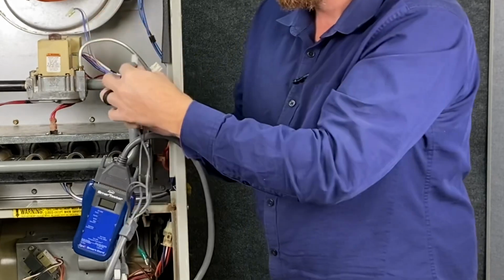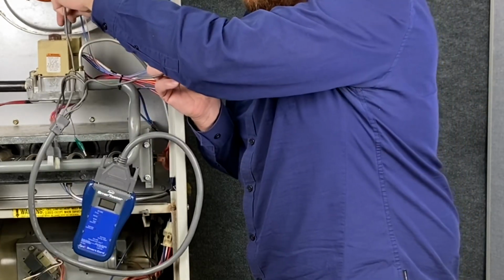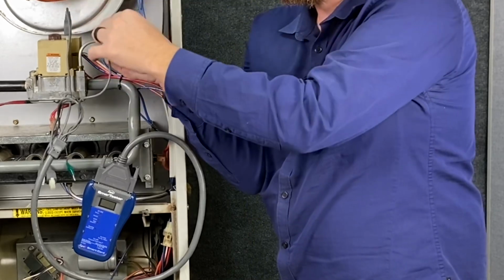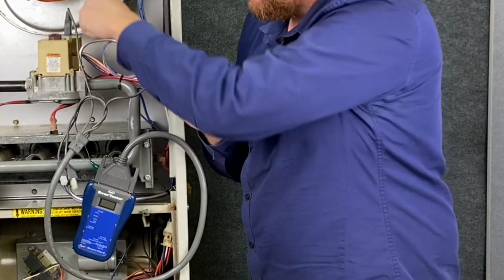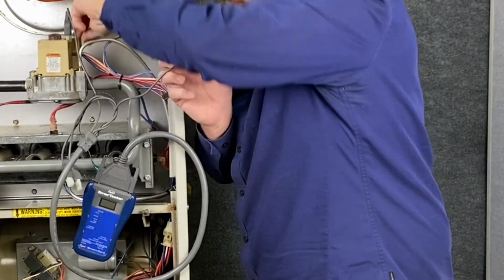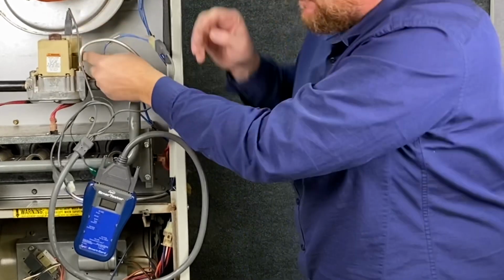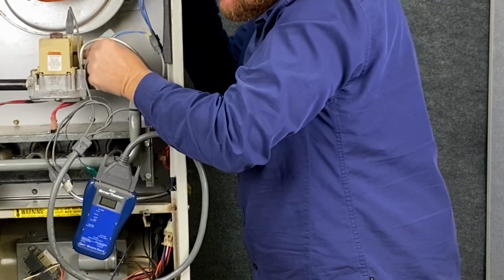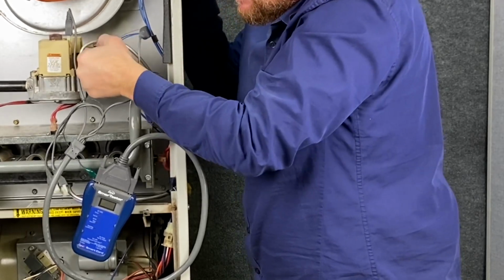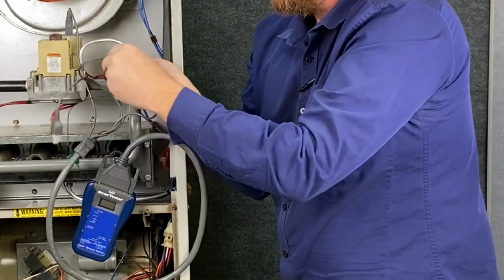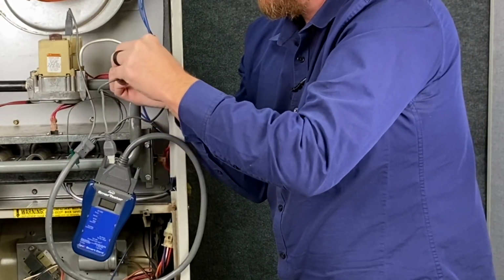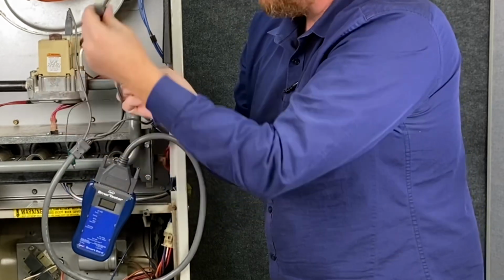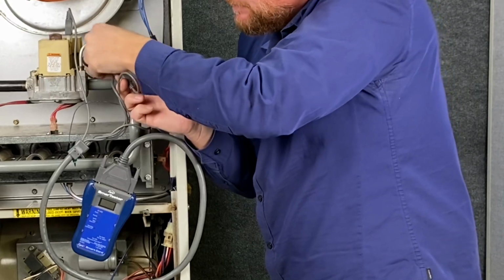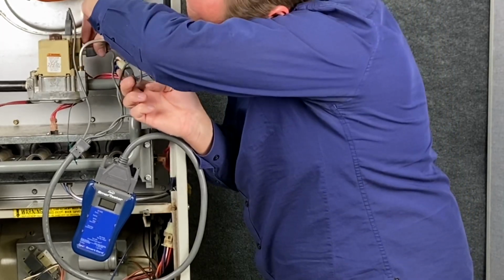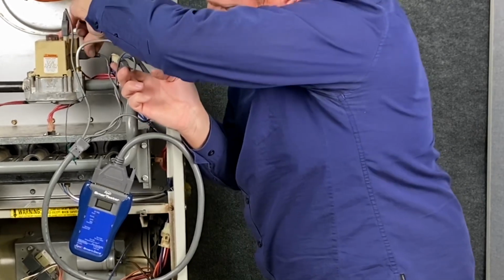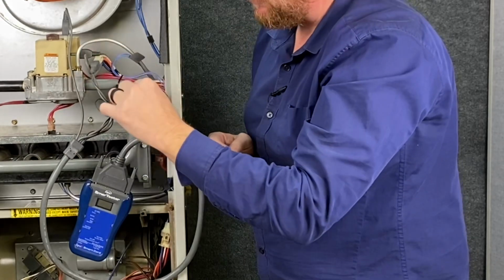This is the igniter, and what I'm going to do is put this fitting into my valve, and then my igniter is going to plug into this component here. I have another plug. It's this little square terminal back here, and I'm going to unplug it as well. And with this little square terminal, we're going to plug it into my meter. And then I'm going to plug this last one back into the smart valve. And then I have to make sure that I have my ground hooked up as well. So I'll hook the ground up.